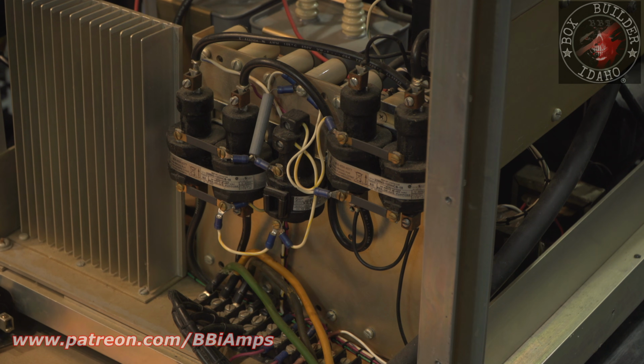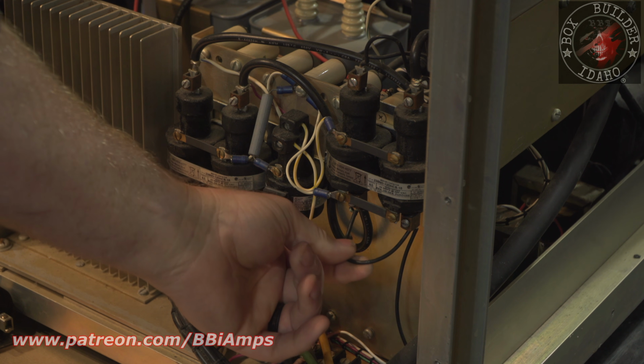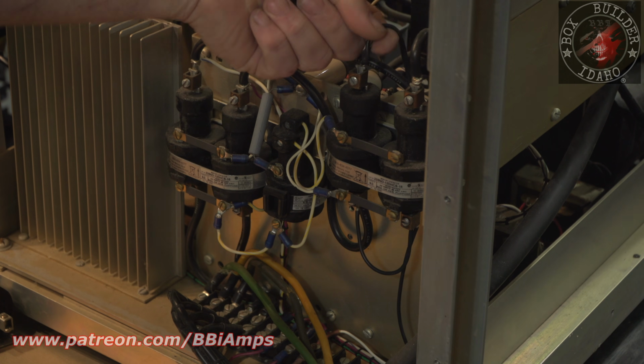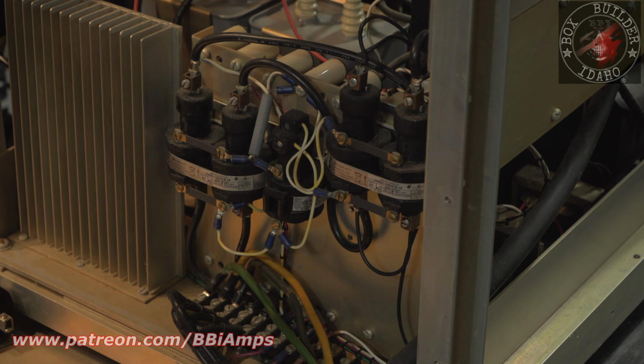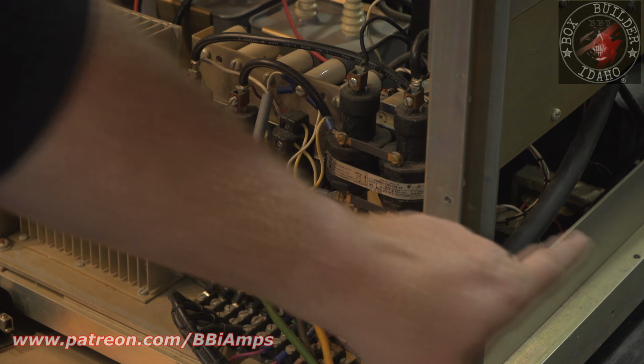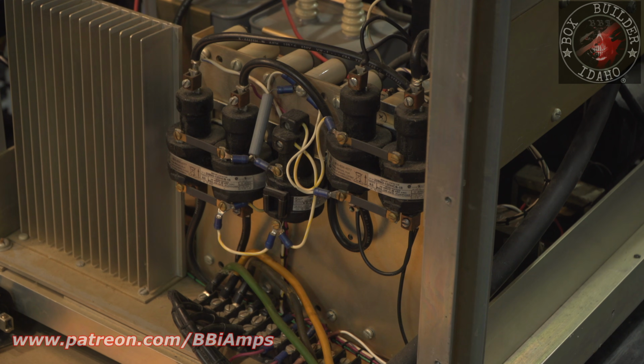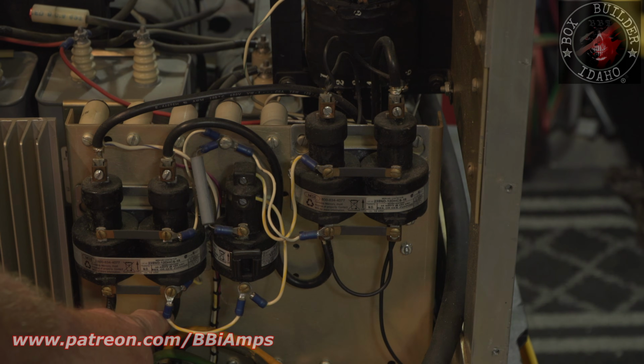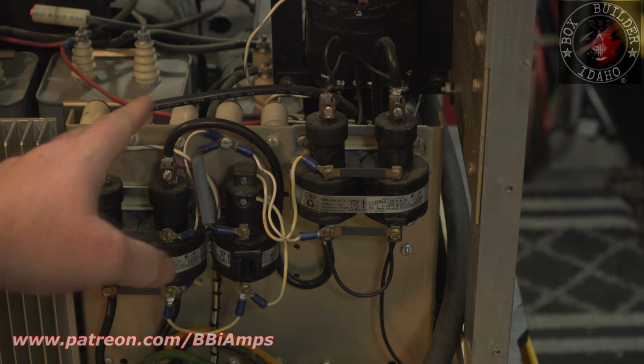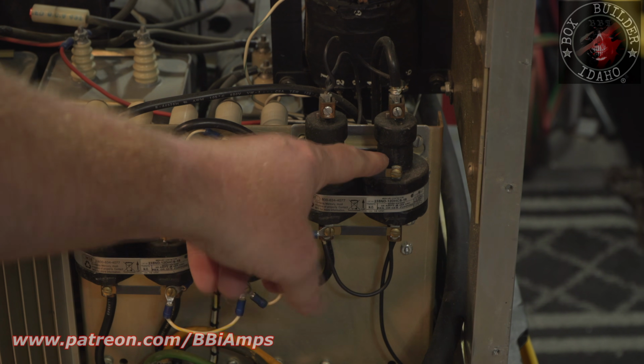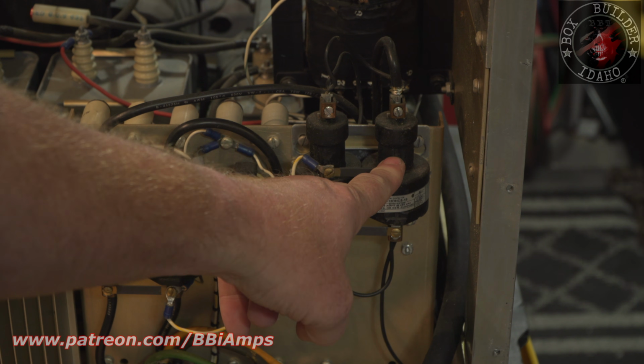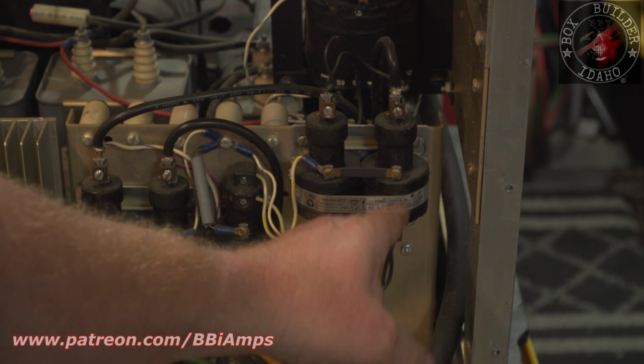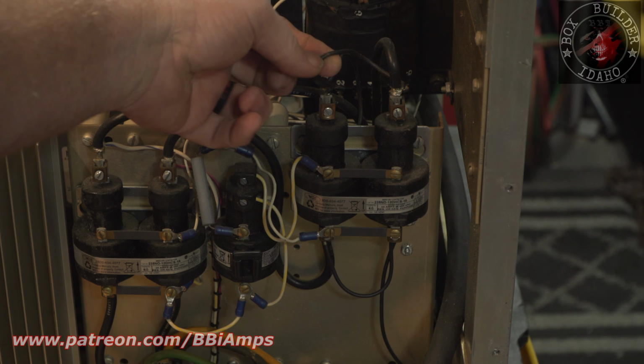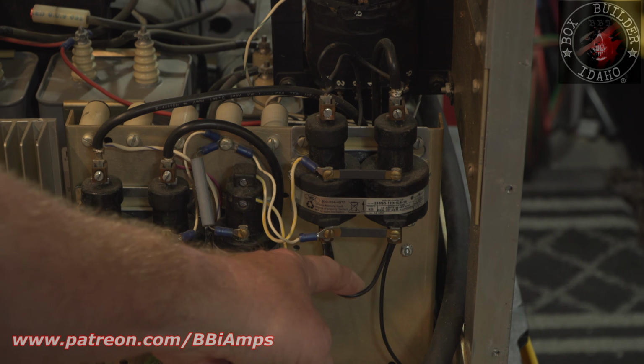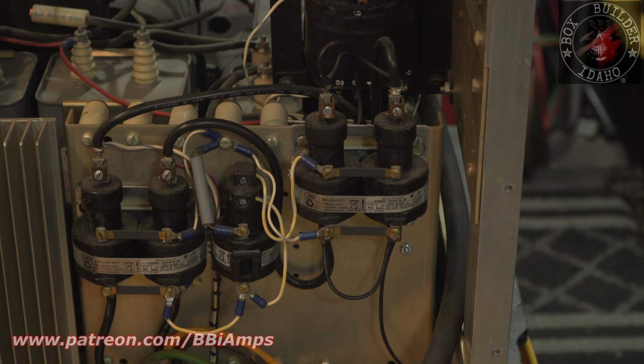Right now the way it's set up is 100% of the juice going through this wire. These leads run off and they run this little secondary supply that's back here. You guys can barely see it. Here, let me show you this from straight on. You see how they're crossing? So that's one leg and that's the other leg, and it comes in, this comes down. This should come over to this contactor, this side of the contactor. Instead, he's got this leg crossed over and this leg crossed over.